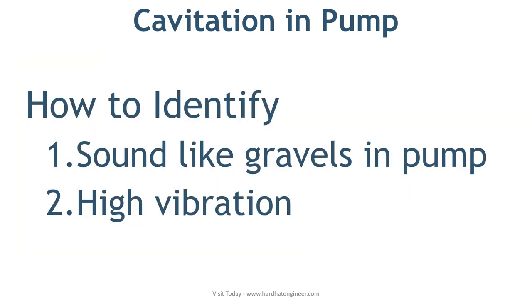You can easily identify where the pump is cavitating by the sound it makes. If you hear a sound that makes you think gravels are being pumped, that is a clear sign of cavitation. Other than this, high vibration is also an indicator of cavitation.